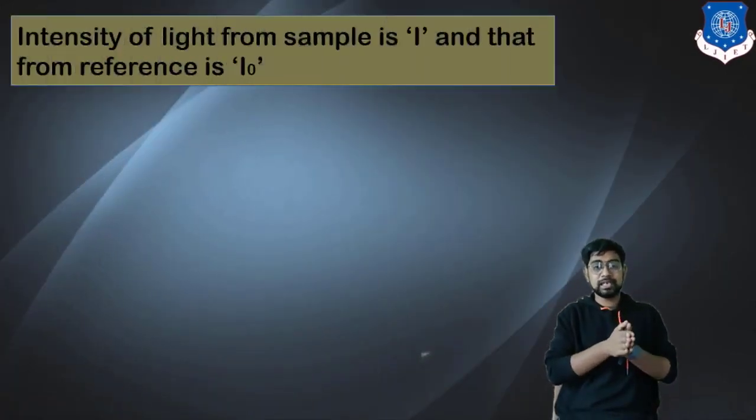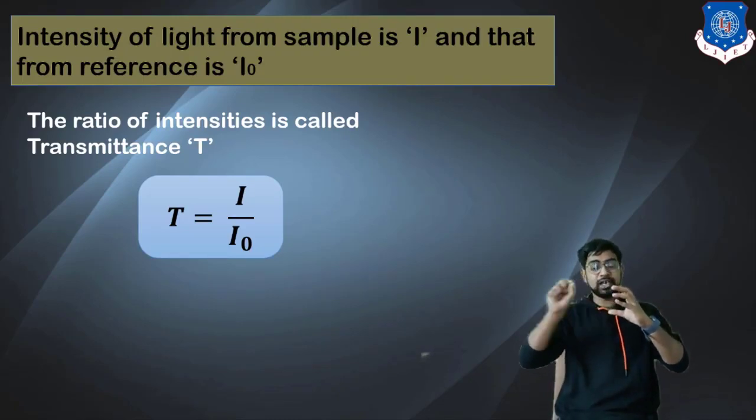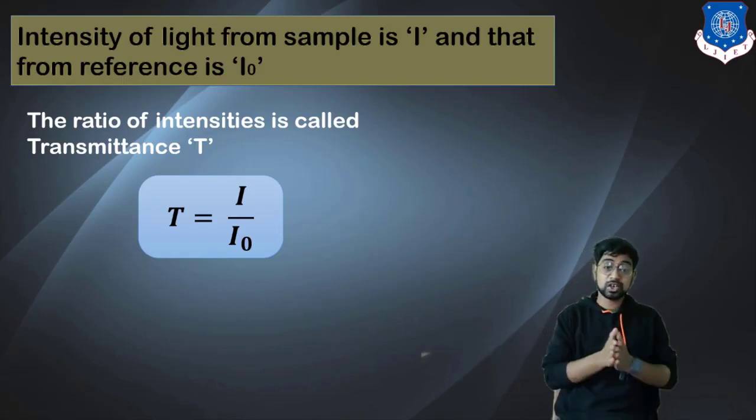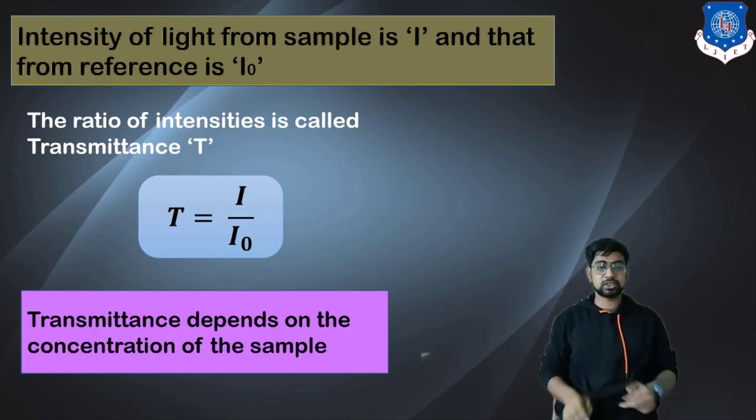How is this functioning? The intensity of light from the sample I and that from the reference I0 would be different. When the light is passing through the reference, a definite amount of light is going through it and the photodiode is detecting. According to the sample's concentration, the light would be absorbed or allowed to flow through it. The more it's allowed to flow through, the more the photodiode would be absorbing. The ratio of intensity is called transmittance: T = I/I0. The transmittance will be dependent on the concentration of the sample.